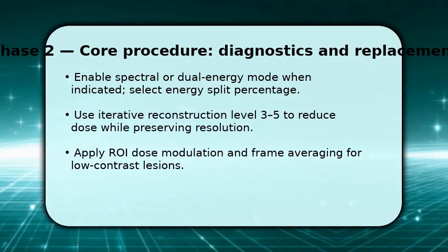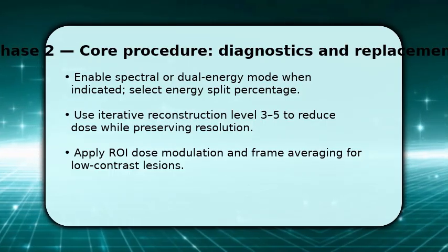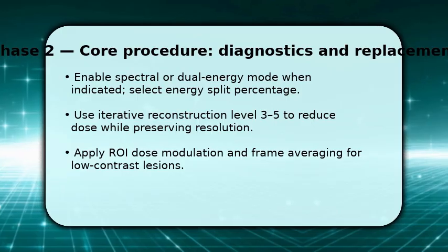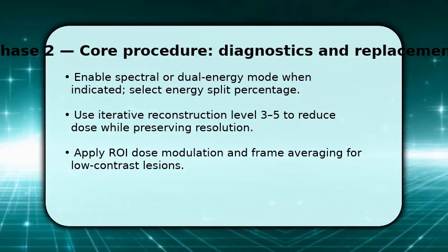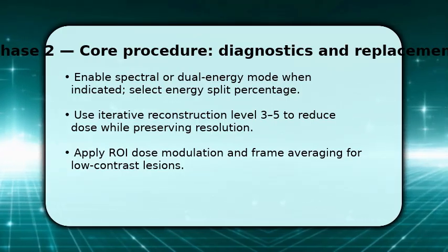Also, engage ROI dose modulation and frame averaging for subtle, low-contrast findings. These reduce noise where needed while keeping overall exposure down.